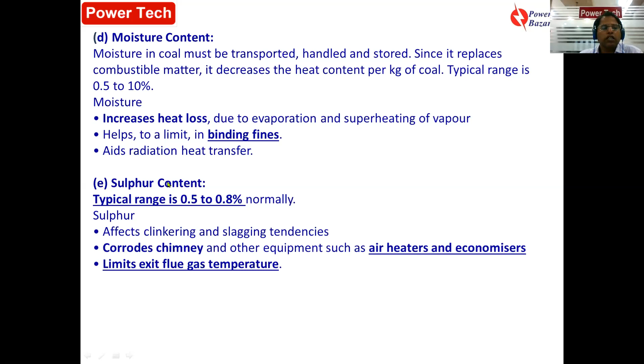Sulfur content is not desirable at all because it corrodes the chimney. As I told you earlier, it affects other equipment, the air heater and economizer, because you get sulfur dioxide plus H2O giving sulfuric acid, and it also limits the exit flue gas temperature. What do you mean by that? If sulfur is not there, I can reduce the exit gas temperature to a certain limit, 200 or 220 degrees centigrade, and I'll save a lot of heat loss. But if sulfur is present, then I cannot reduce the exit gas temperature. What will happen if I reduce it? Water vapor will condense and stick to the chimney, or it will corrode the chimney. Therefore, because of sulfur, I cannot limit the exit flue gas temperature.